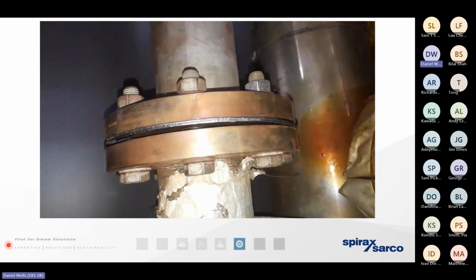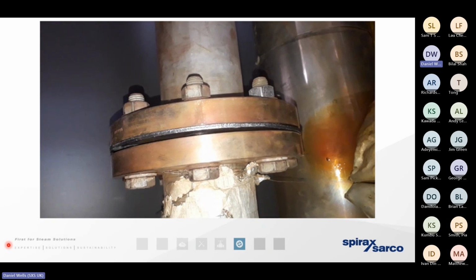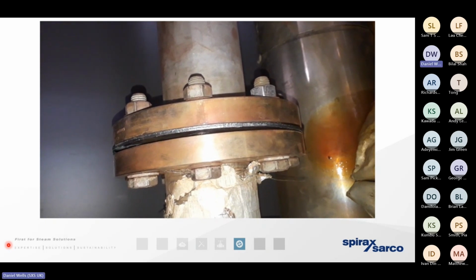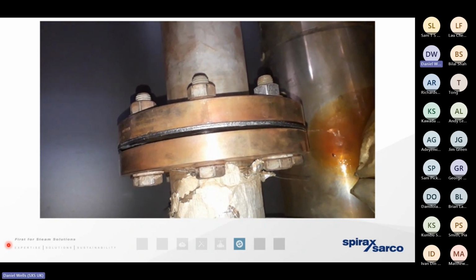The video I'm showing at the moment is a gasket that's blowing. We've got a pressurized steam pipe that's pushing that condensate along, and it's resulting in some of that water hammer that we've spoken about. The water hammer has actually caused the gasket to rupture on this occasion. What's likely to happen here is that in 5, 6, 7, 8 weeks' time, the engineering team will have the opportunity to close off the steam system, let it cool down and depressurize. They'll pull apart those flanges and they'll probably replace the gasket. The problem is, as soon as the steam system is re-energized, the exact same thing will happen.